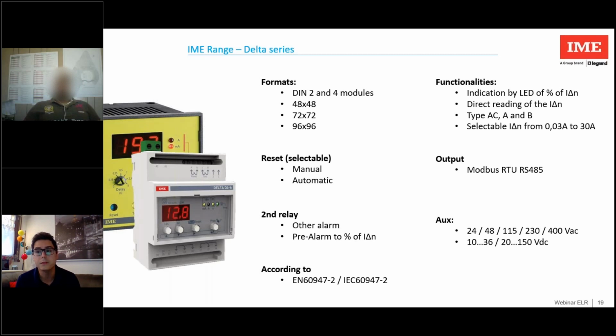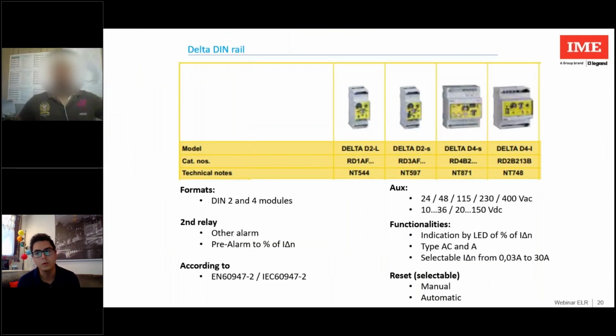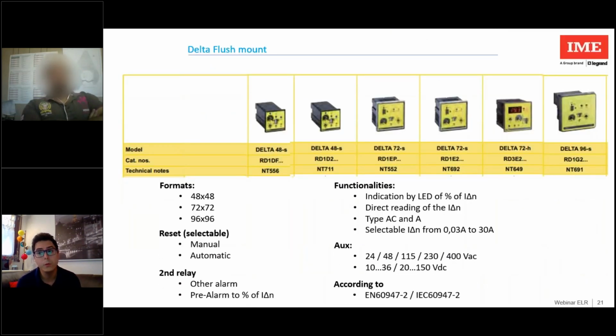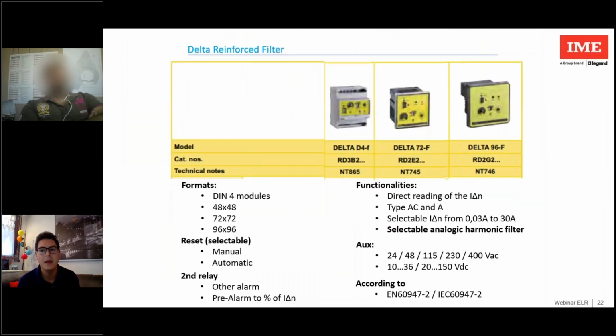For the rail instruments, we find from 2 to 4 modules, which mainly differ in the quantity of alarms, 1 or 2 alarms, and in the percentage indicated through a LED bar. All these ranges are for the type A and AC. For the flush mount, we find different dimensions, as mentioned a little while ago, and also here a possible bar indicating the percentage of differential current with respect to the set threshold. In the range, there is also a model with a display capable of displaying the differential current value. The instruments mentioned so far are in class A and AC.